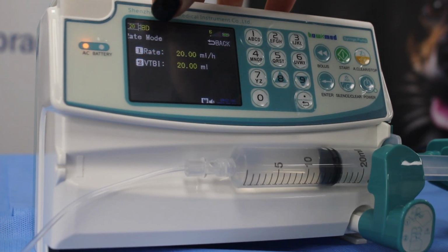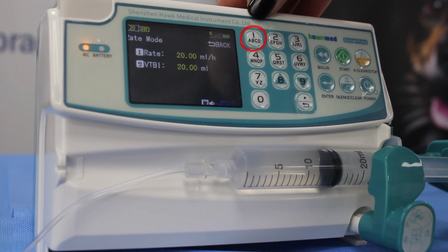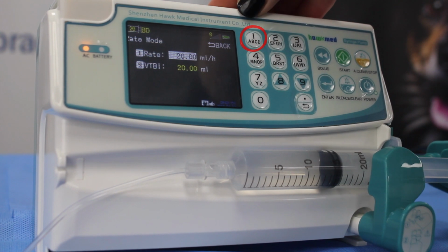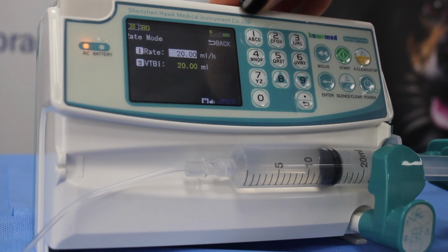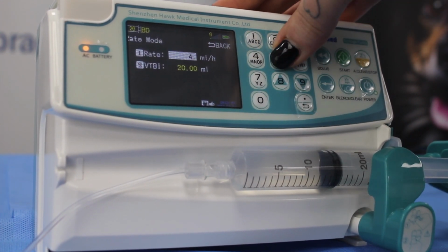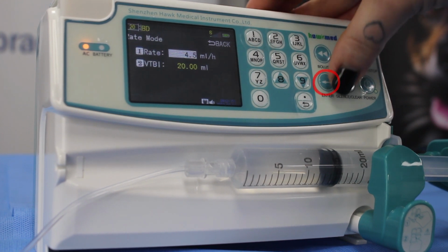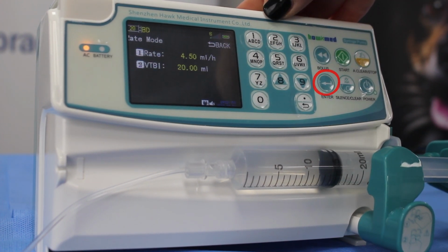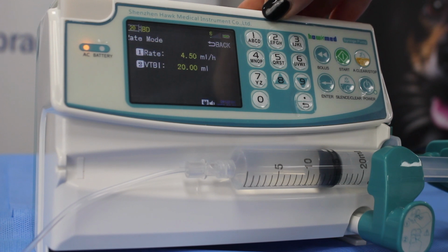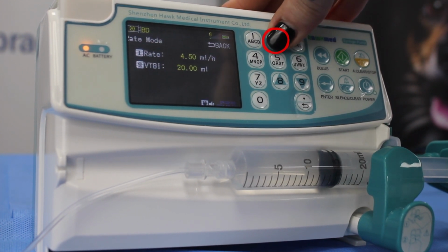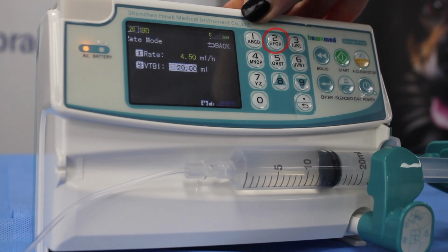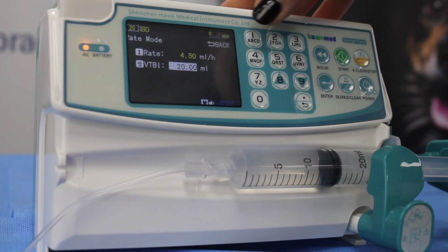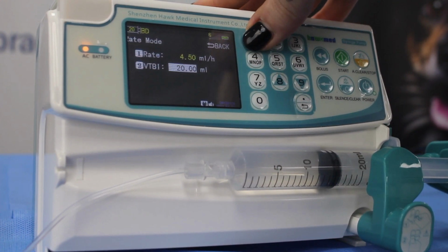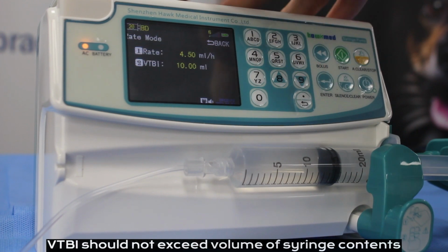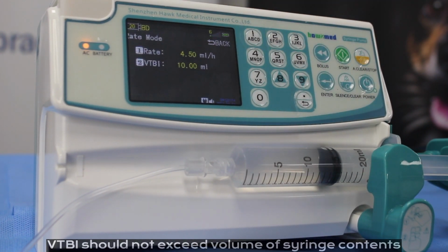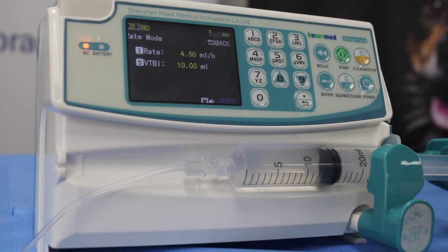To adjust the rate, we just need to press our corresponding number, which is 1, and we can adjust this on our number pad. We must press enter to confirm this adjustment. For volume to be infused, we press number 2, and we can input the total volume to be infused in here. This pump is now ready to start infusion with your patient.